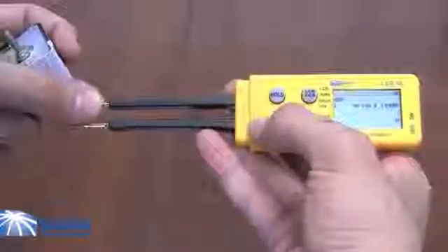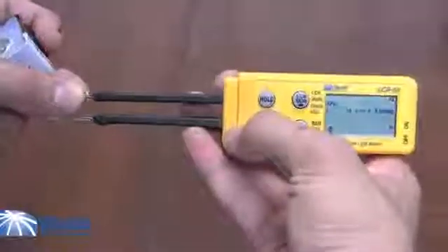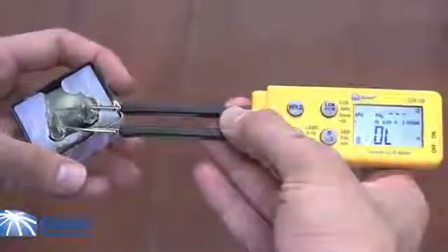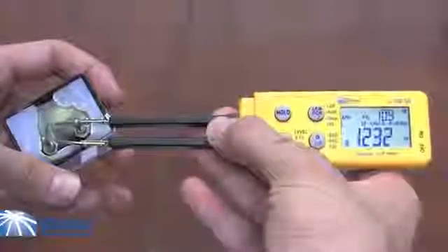When we use a different frequency range, we can see that our accuracy is not optimized. Now, we will use a 10 kHz setting, and as you can see, our precision has been lowered.